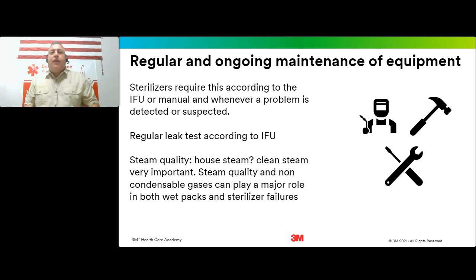Leak testing - okay, we're not talking about Bowie Dick testing. Sterilizers, and this has been big lately with the auditors, accreditation agencies - your sterilizer can perform a leak test. Look to your IFU, that's one of your assignments. If you take away anything, it'll take you 5 minutes - just go and look for your IFU and see what the IFU for the sterilizer says regarding the leak test. It's going to tell you when and how often you should potentially run the leak test.